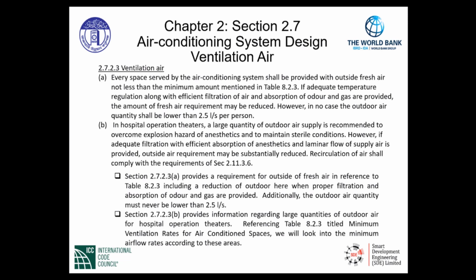If adequate temperature regulation along with efficient filtration of air and absorption of odor and gas are provided, the amount of fresh air requirement may be reduced. However, in no case the outdoor air quantity shall be lower than 2.5 liters per second per person. When we read this section, there's a whole bunch of information in this section. What this section is talking about is what we call mechanical ventilation. And it gives a very specific table.